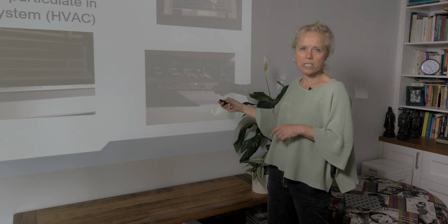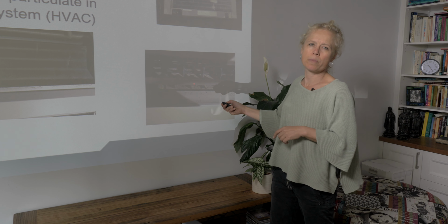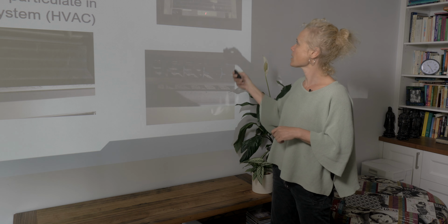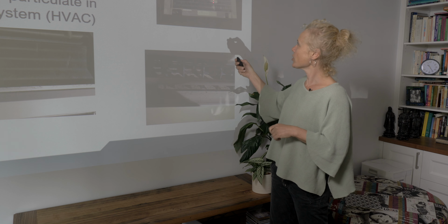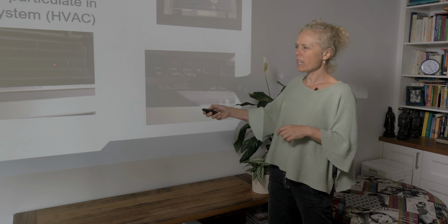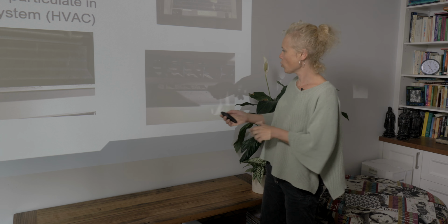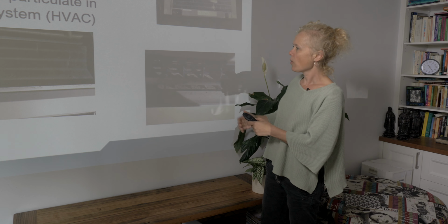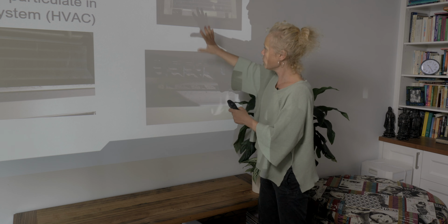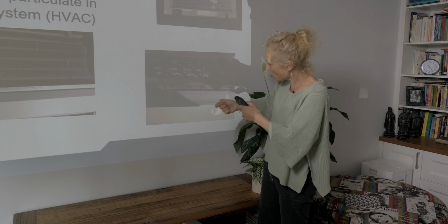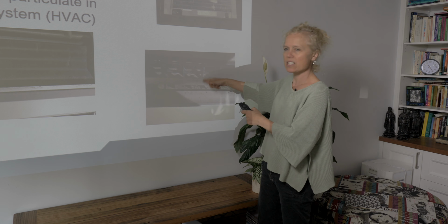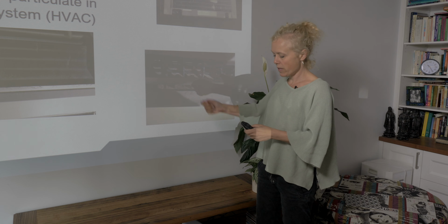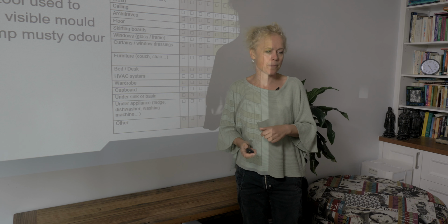They had high levels of Aspergillus, Penicillium, and Cladosporium, which we often find in contaminated heating, ventilation, air conditioning systems. Condensing coil, very dirty here, but generally with the HVAC system, what you're looking at is, with a torch, looking underneath where the barrel fan is. This is the barrel fan here, and you've got the condensing coil at the front, and then with the torch underneath looking at the barrel fan, because that's where often the fungal particulate tends to be at its highest. If you can get a swab there or sample, that's highly recommended.